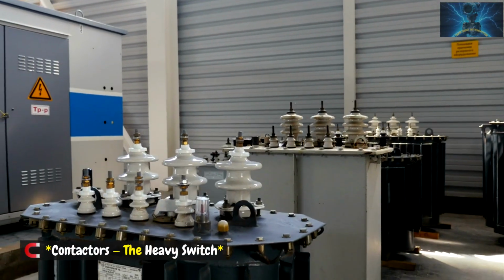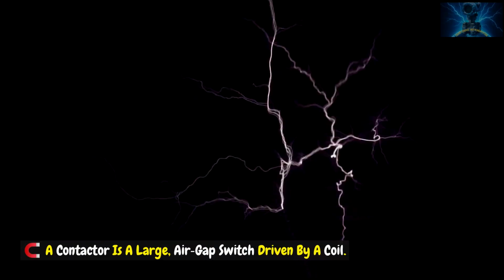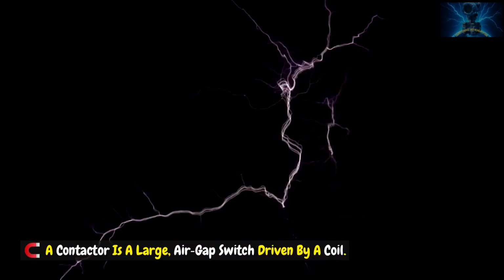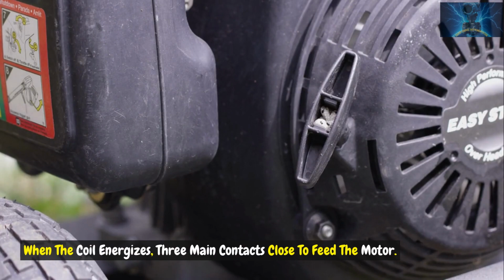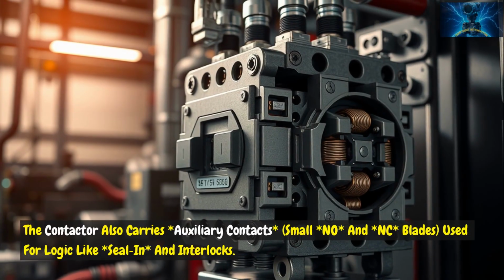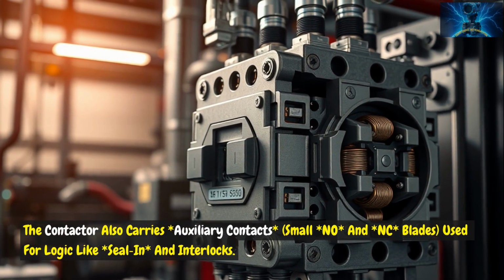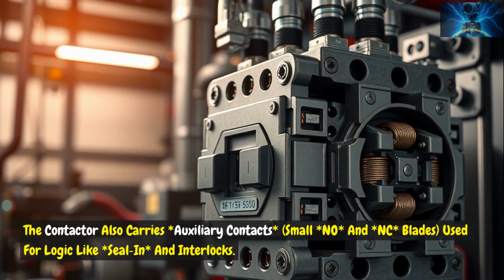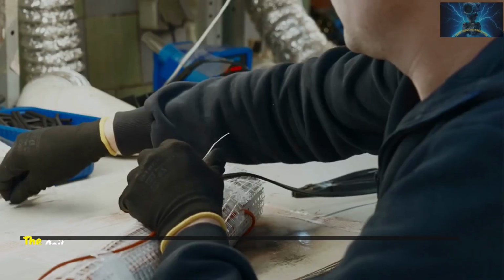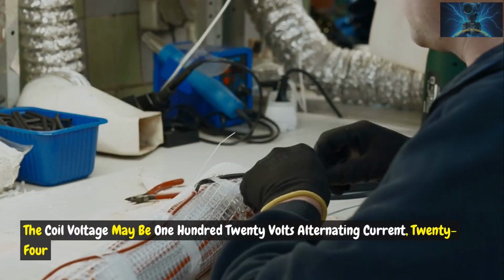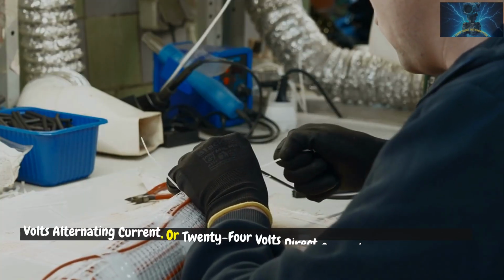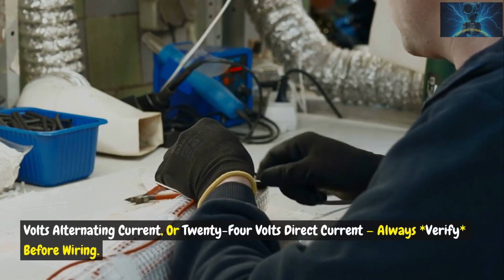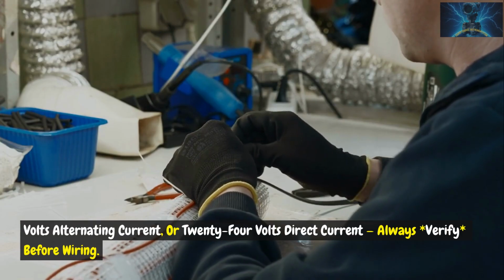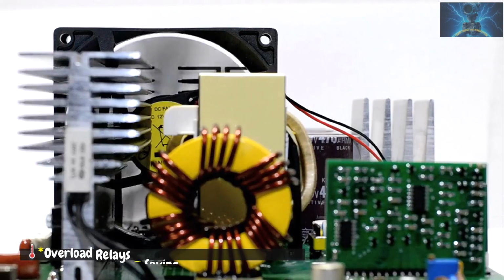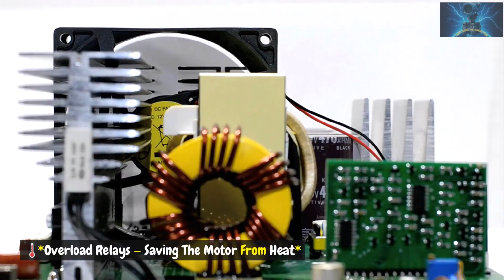Contactors, the heavy switch. A contactor is a large air gap switch driven by a coil. When the coil energizes, three main contacts close to feed the motor. The contactor also carries auxiliary contacts, small NO and NC blades, used for logic like seal-in and interlocks. The coil voltage may be 120 volts alternating current, 24 volts alternating current, or 24 volts direct current. Always verify before wiring.